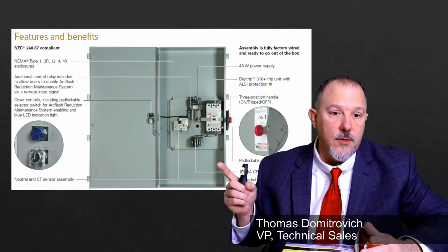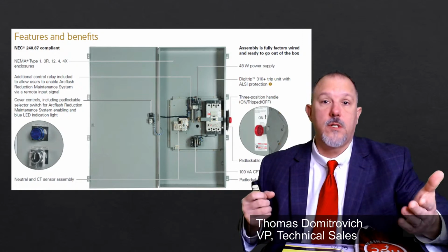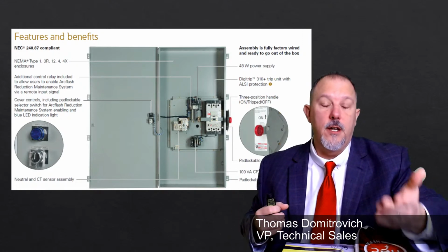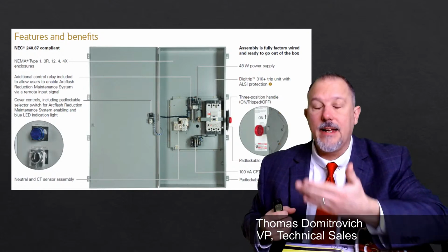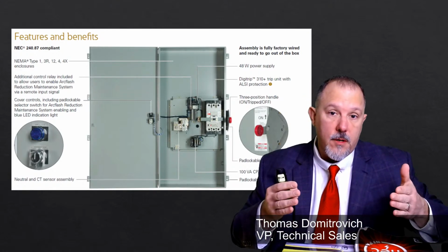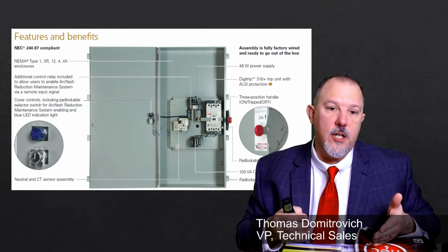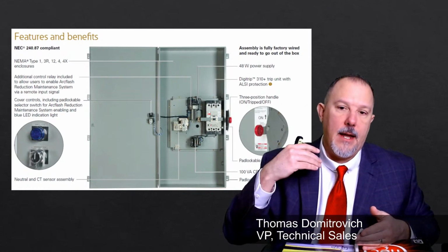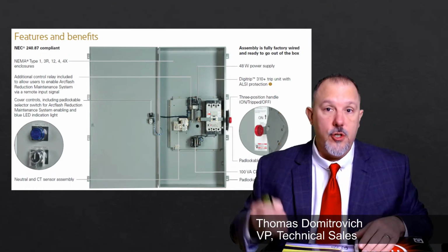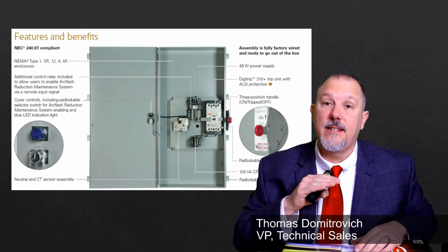Over there on the right, you'll see the little blue light. What's the blue light? The arc reduction maintenance switch. It has the ability to lock and tag out. So you can turn on the arc reduction maintenance switch, lock and tag it out, and what you've done is reduce the severity.